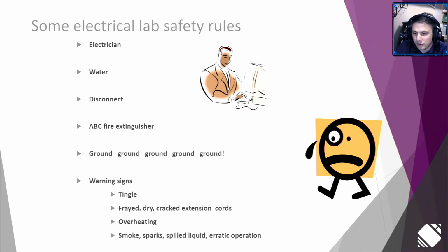Electrical cords are designed to be very flexible. They're designed to be temporary, and unfortunately that means they get stepped on, they get wheels of equipment run over them. They can certainly get damaged over time, and they need to be inspected before use to make sure they're safe. A grounded plug with the third prong cut off.